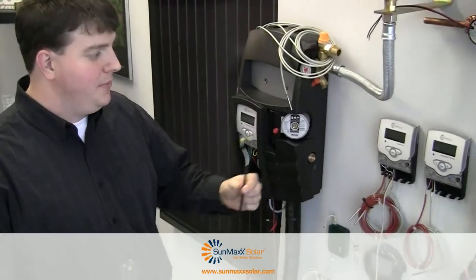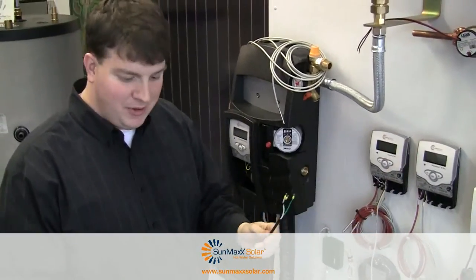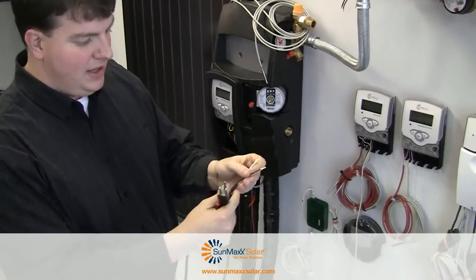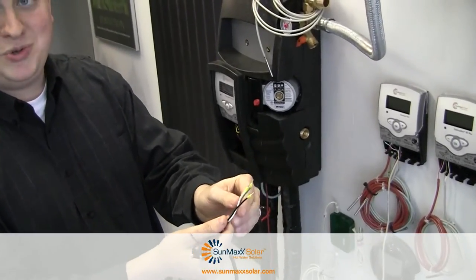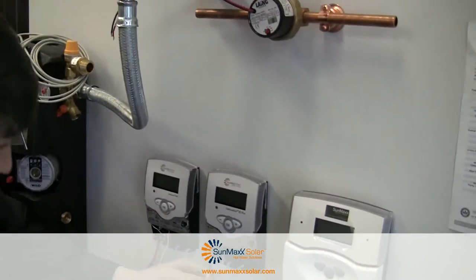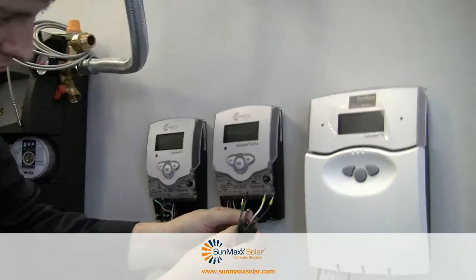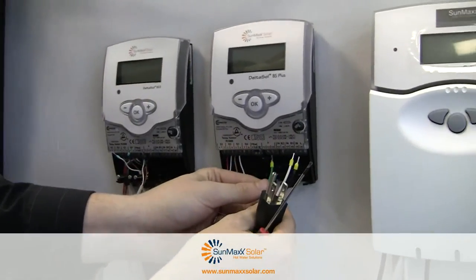The next step after you have your sensors installed is to give the controller some power. This comes with a three-prong power connector, so we have a live port, a ground port, and a neutral. We're going to connect this to the controller: black goes in L20, white goes in N19, and the green goes in 12.